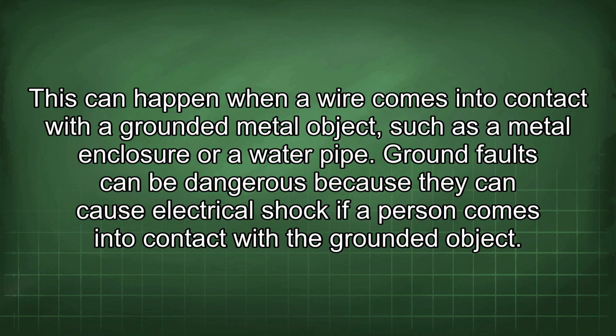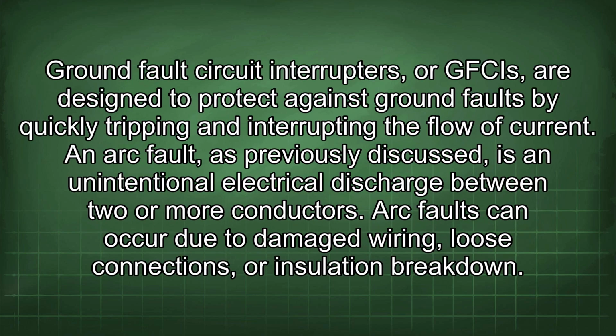Ground faults can be dangerous because they can cause electrical shock if a person comes into contact with the grounded object. Ground fault circuit interrupters, or GFCIs, are designed to protect against ground faults by quickly tripping and interrupting the flow of current. An arc fault, as previously discussed, is an unintentional electrical discharge between two or more conductors. Arc faults can occur due to damaged wiring, loose connections, or insulation breakdown.